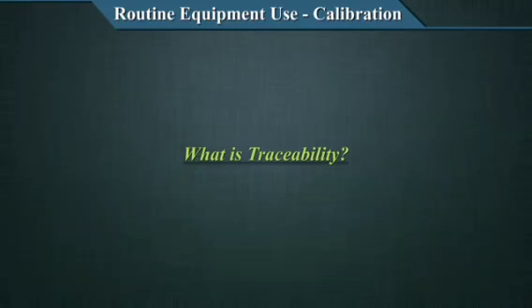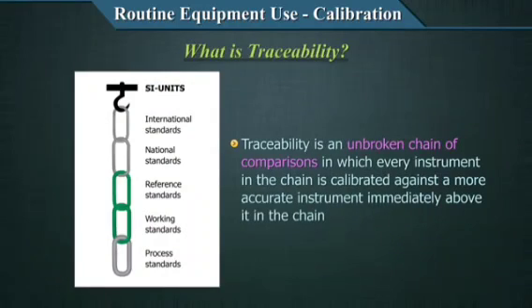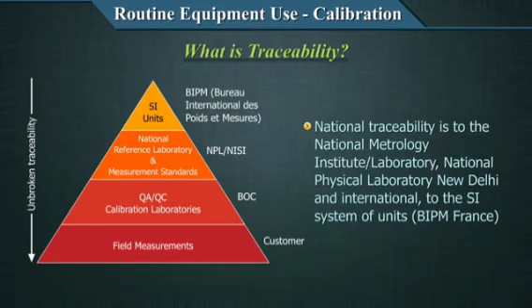Since this is a new concept, I would like to reiterate with another illustration. Traceability is an unbroken chain of comparisons. Look at the links in this chain, in which every instrument in the chain is calibrated against a more accurate instrument immediately above it in the chain. Remember the picture from before? Calibration thus is the linking of measurement standards and or measuring instruments to relevant national or international standards through an unbroken chain of comparisons. Again, to reiterate, national traceability is to the National Metrology Institute or Laboratory, NPL, New Delhi, and the international to the SI system of units at BIPM, France.